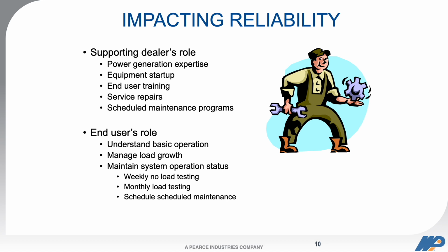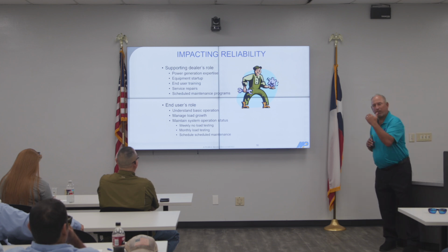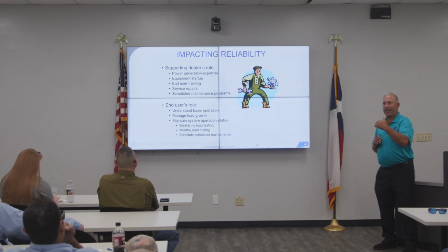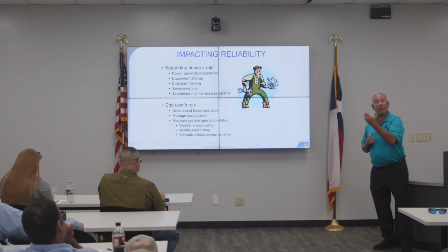End user training - that's a really tricky one too. A lot of people want it, a lot of water people want this as well. The problem is that generally when we're there for startup, no one else is there. The contractor's just finishing up, we commission the generator, maybe the AHJ or fire marshal's there, but you guys aren't there yet. The people that need to know the operation of the generator aren't on site yet. So a lot of times we'll talk to people - we find this piece to be very important, but I don't want to put that money in at the front end because it will make us uncompetitive, and then no one gets the training. So it's a very important piece that needs to be discussed, but it's hard to do during the commissioning time.